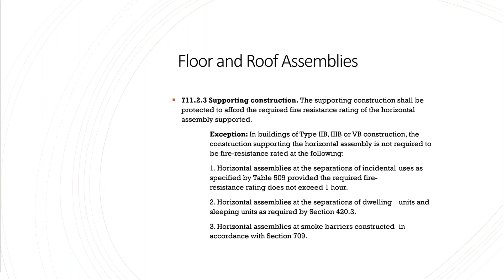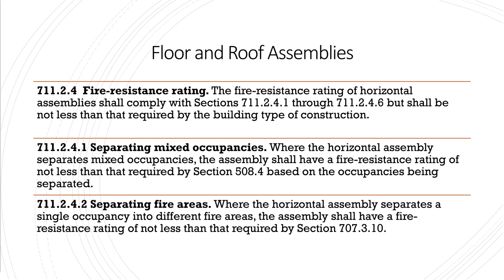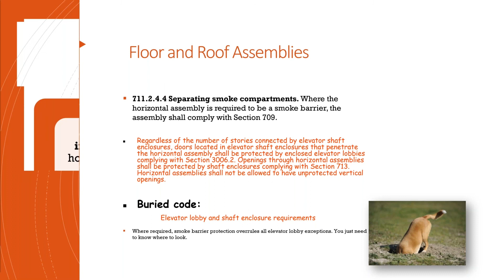What is the rating needed for those? So go to 241 through 246. But again, there will be specifics in other portions of the code that will tell you what these assemblies have to be rated. When you're separating mixed occupancies, go to 508.4; separating fire areas, 707.3.10. There's also requirements for dwelling units and sleeping units. When you're separating smoke compartments, you also look at 709. And don't forget lobbies, there are requirements there for lobbies. You have to have that smoke containment at those lobbies as well. Even though your shaft is protected, you've still got smoke compartmentation that has to happen floor to floor. You see that with a lobby or smoke containment.